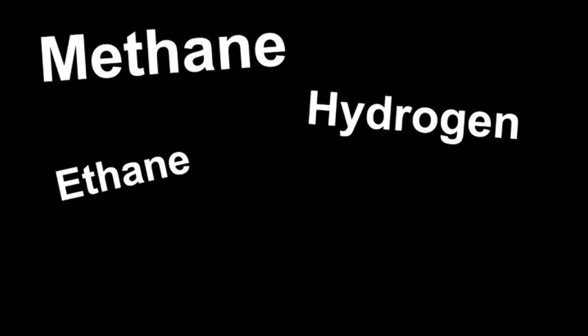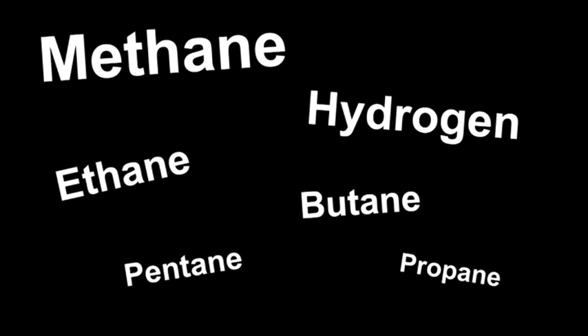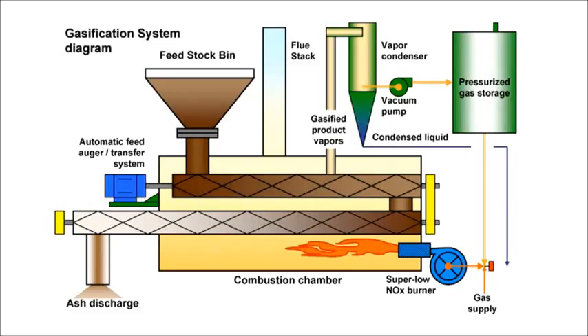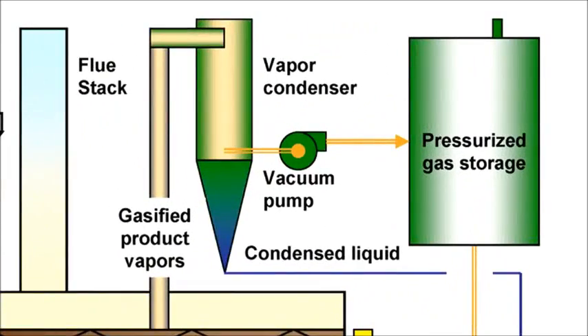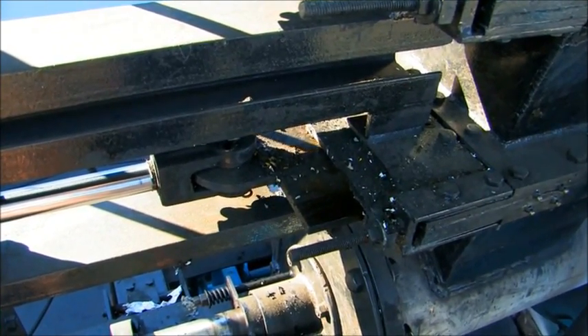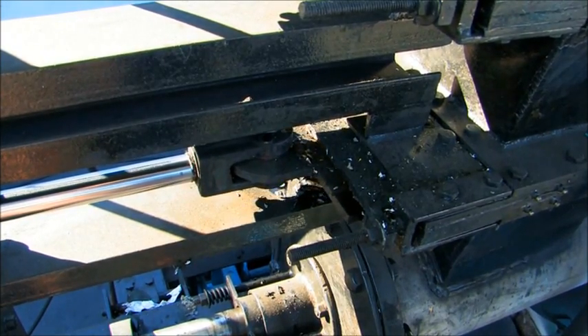This heated environment is oxygen deprived, ensuring the feedstock never burns, but rather is distilled into its basic chemical components, which are all flammable and energy-rich. This pyrogas is removed from the retort, pressurized, and then stored. The feedstock enters the retort through a double-valve airlock, where a vacuum is pulled to ensure the retort remains oxygen-starved.